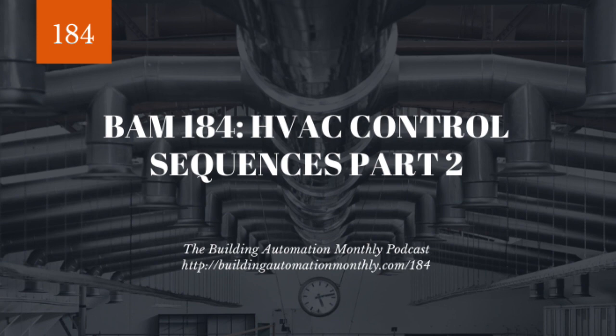Additionally, now we start to introduce this concept called economizer, which basically is a way of using outdoor air that is cold so that we don't have to cool down the air. Pretty nifty, right? Take advantage of that. It's also a way of using the outside air damper. Well, this isn't called economizing. This is called actual demand ventilation, where we open up the economizer to a point to allow the appropriate amount of fresh air in, so that our occupants aren't breathing CO2 and passing out, because we want them to have fresh air so that they stay awake and they get enough oxygen.